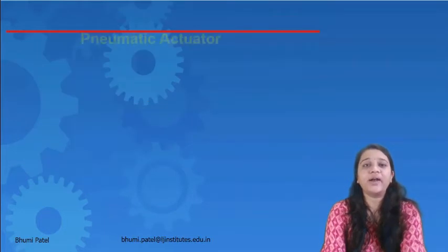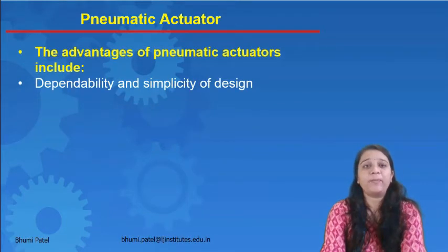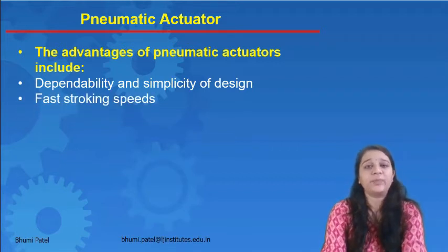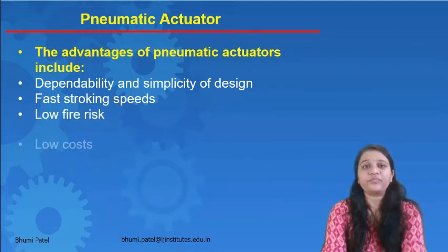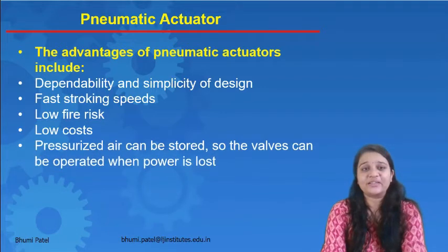Now what are the advantages of pneumatic actuators? They offer dependability and simplicity of design. Simply, we can connect our actuator to the top of the control valve. Also, fast stroking speed, low fire risk, and the cost of the pneumatic actuator is low. Its pressurized air can be stored, so the valve can be operated when power is lost.